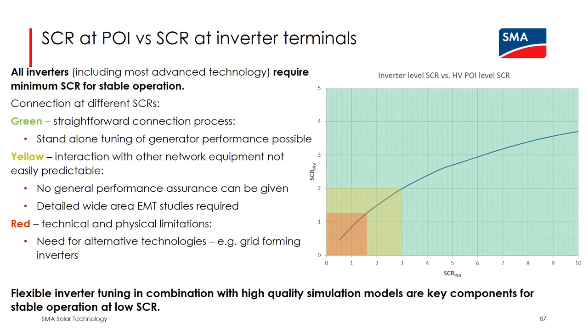So when talking about low SCR, it is important to understand that all inverters which are running as asynchronous generators require a minimum SCR for stable operation. We as a manufacturer, for example, give a certain number to which SCR we guarantee stable operation of the inverter. But here one needs to understand that SCR at the inverter is different to the SCR at the point of interconnection.